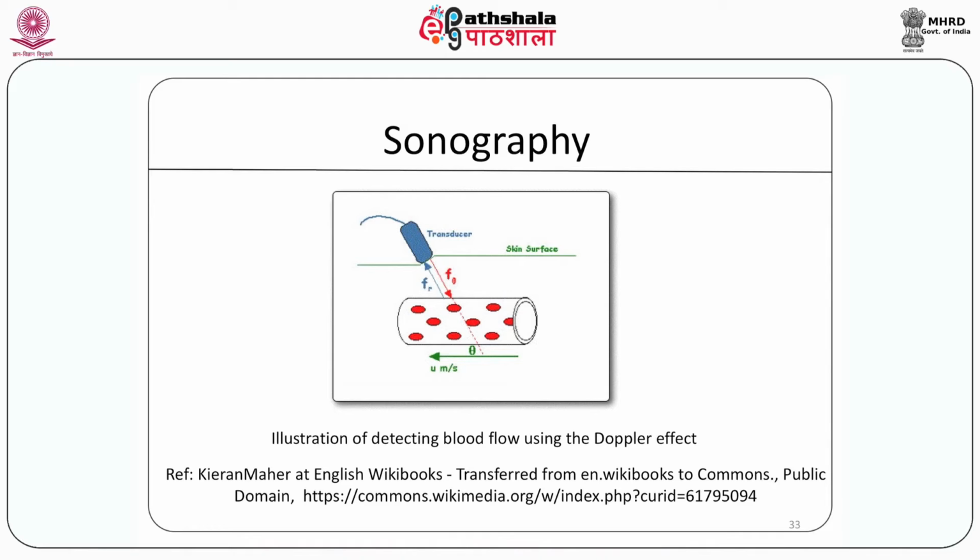The probe in this imaging equipment is mechanically coupled to position resolver, which makes electrical output. Imaging is done by moving the probe on the surface of the skin and developing a 3D image using a computer. Thus, it is possible to construct anterior and posterior, lateral and cross-sectional scans of blood vessels.